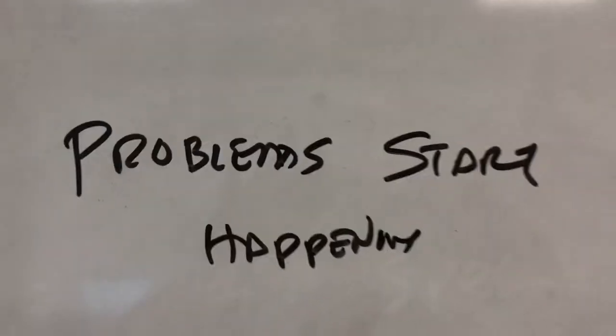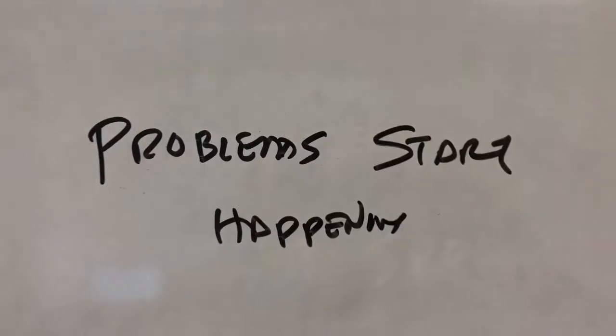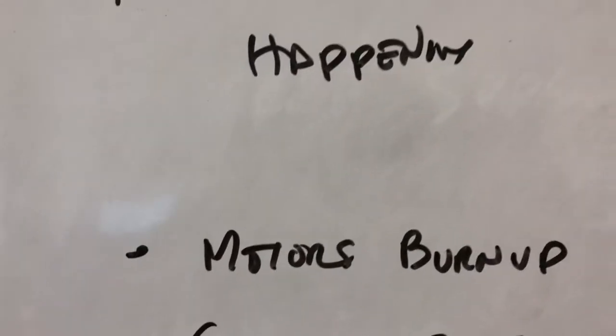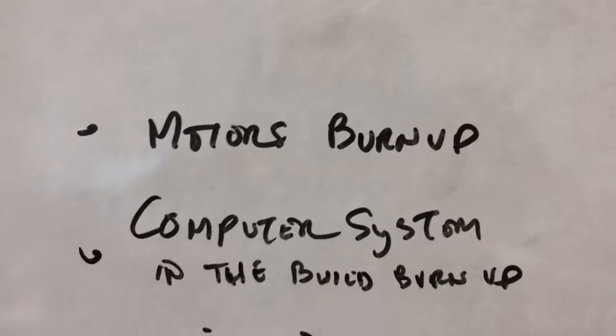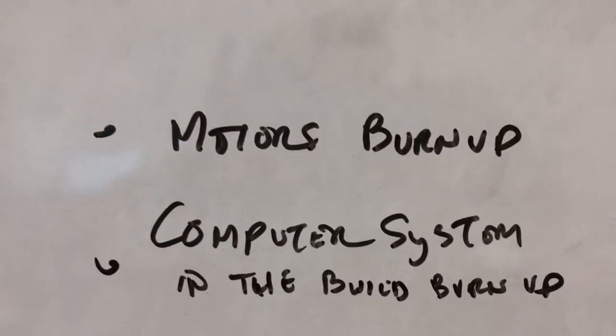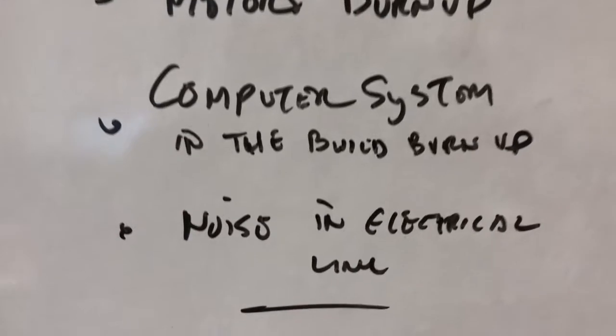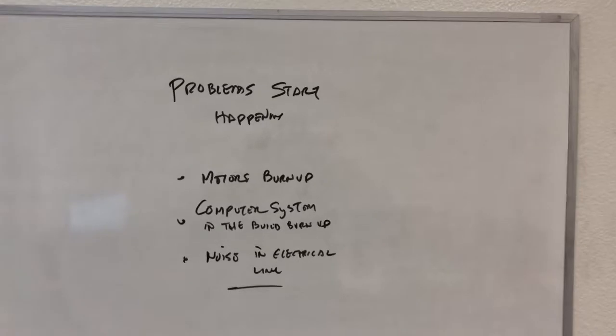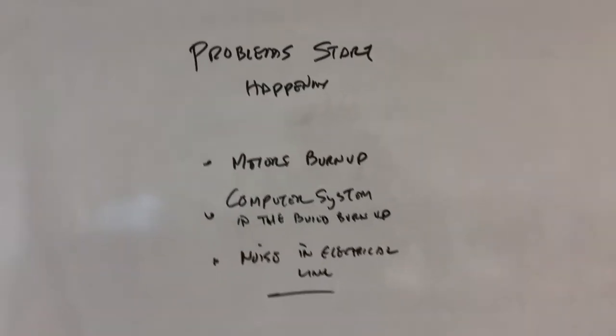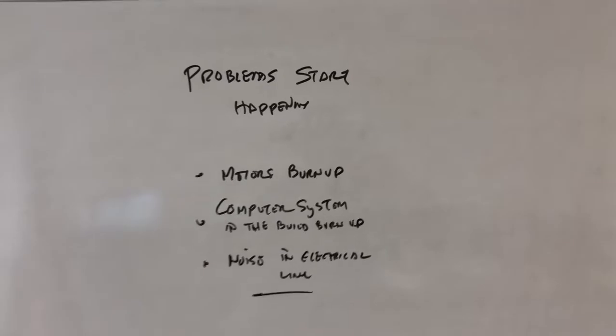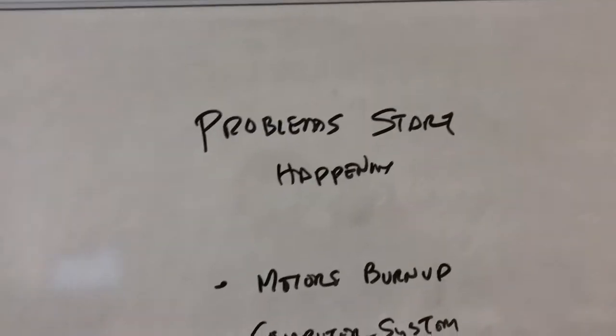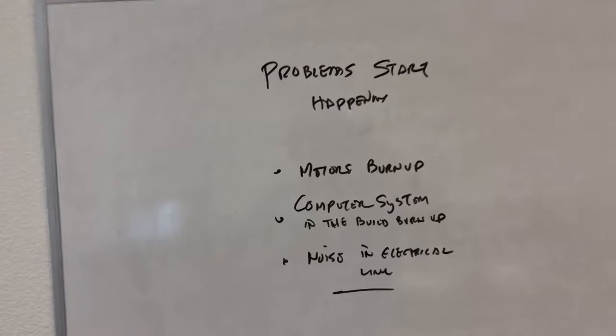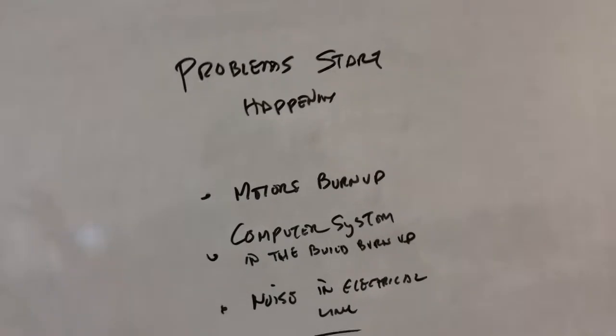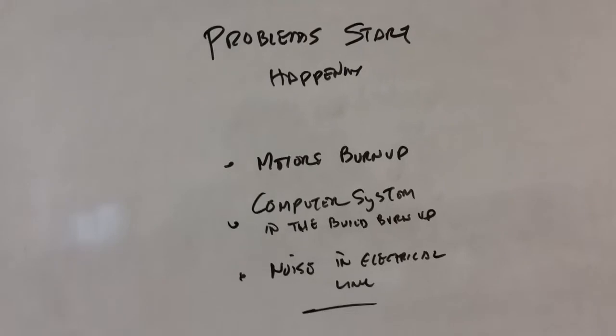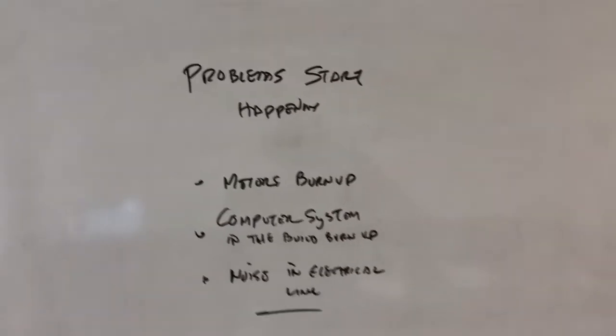All kinds of problems start happening because VFDs are becoming common, people are saving money and energy, but motors start burning up. Computer systems, laptops, desktops, even mainframe systems, start to burn up because of electrical noise on the line caused by the VFDs. Remember, the VFD is now classified as a mechanical item, so there's never an electrical engineer looking at it or evaluating it. It's just mechanical engineers who know nothing about VFDs, taking the manufacturer's written specification and inserting it into their documents without anything else.